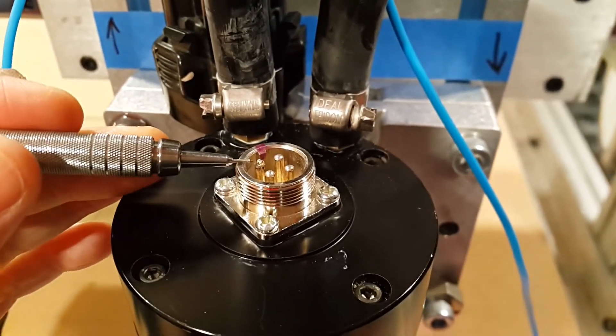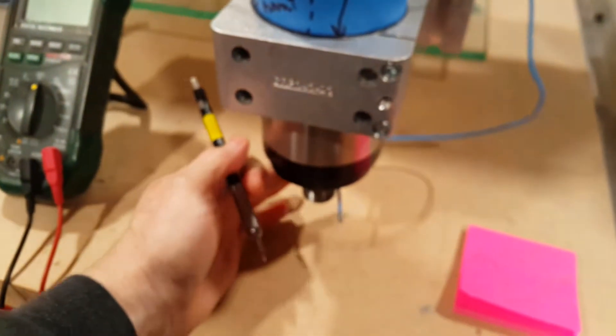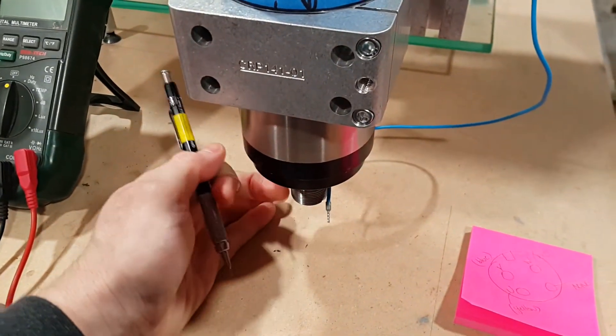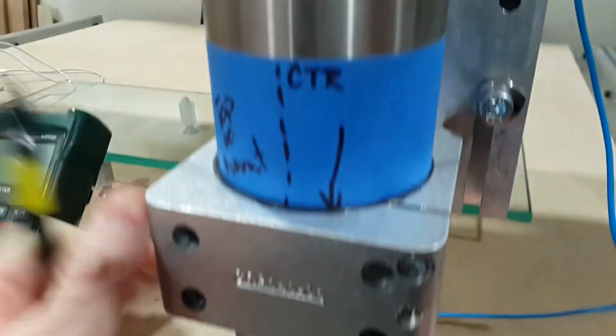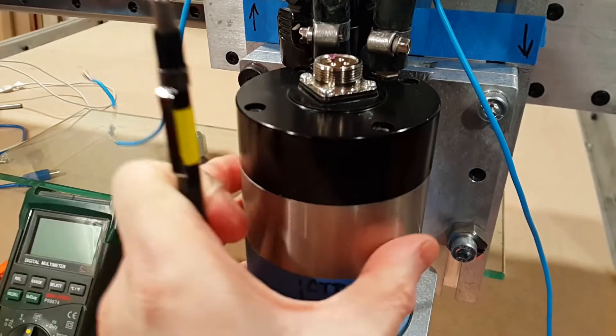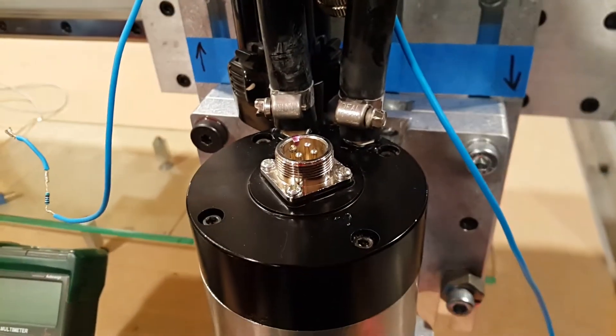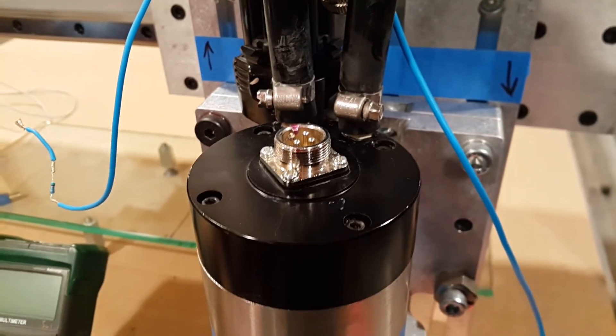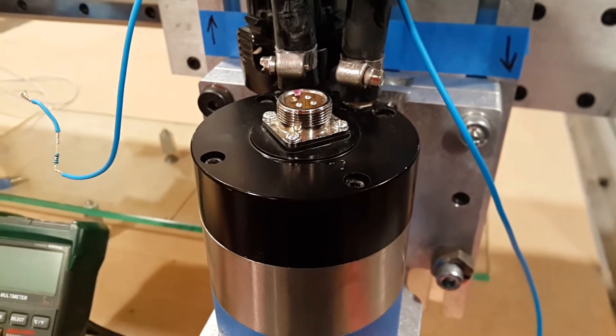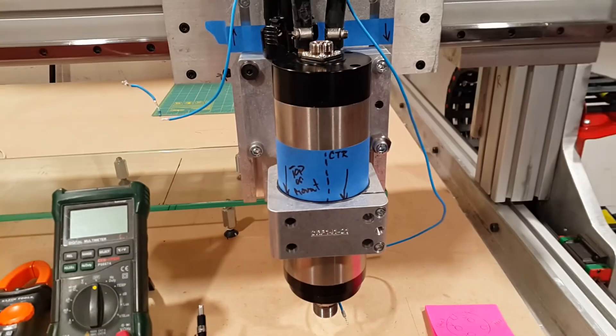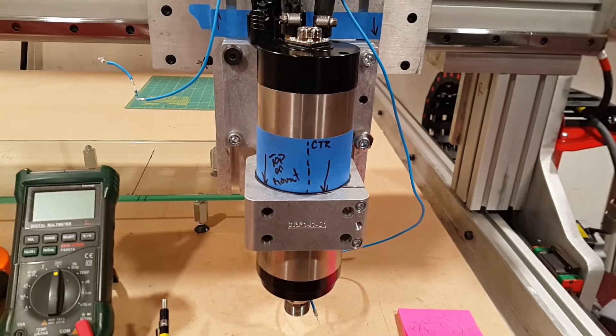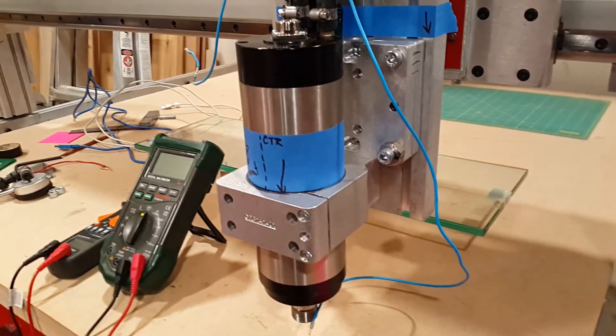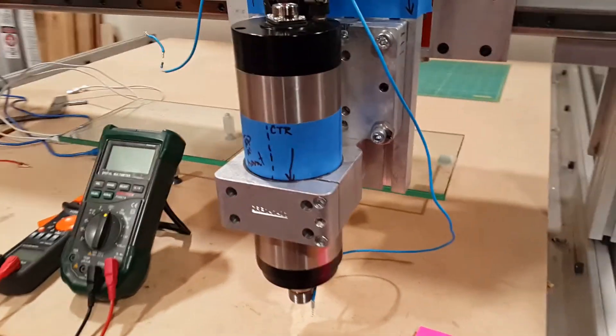The task at hand is to measure the stator resistance. The spindle has two main components: the rotor which is contiguous with the part that spins, and the stator which is the windings of the motor that stay stationary. My VFD wants to know what the stator resistance is for the spindle, and I have no idea. I can't find it published anywhere. I emailed the source I got this from and they didn't know either. They supposedly were going to forward the question to the manufacturer and I've never heard back, so I've pretty much given up getting that information.